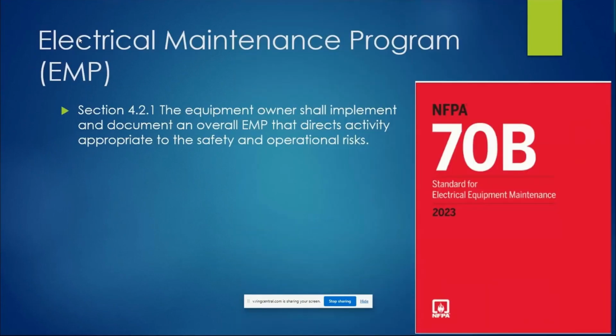Now, the electrical maintenance program is the other part of this. Documentation. You have to document everything you do. Make sure you develop a standard or program within your own organization with your company's letterhead or headers. The document needs to include, at minimum, the schedule for the equipment, and you have to identify the equipment within your schedule, like switchgear room 1, switchgear room 2, switchgear room 3, and so on.